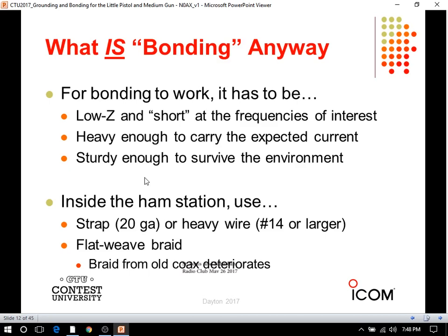For bonding to work, for this connection between pieces of equipment to work properly, it has to be low impedance and electrically short at the frequencies of interest. If we're talking about a 2-meter station, what's the wavelength? Well, 2 meters. So you want to keep all your connections less than a 10th or a 20th of a wavelength long. That's pretty short. If you're talking about HF, they can be longer. If you're talking about AC, they can be quite long. But they have to be short and low impedance so that when the connection is made, it doesn't look like an inductor, an antenna, or a transmission line. It looks like a short circuit. Keeping things short and low impedance makes them a short circuit.